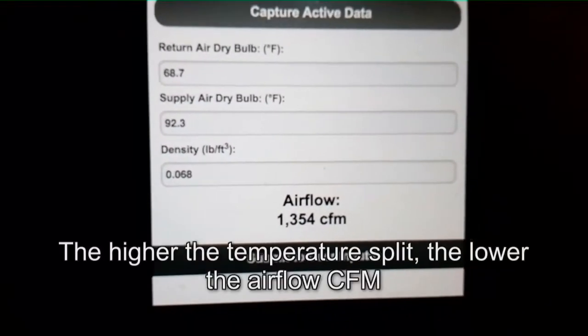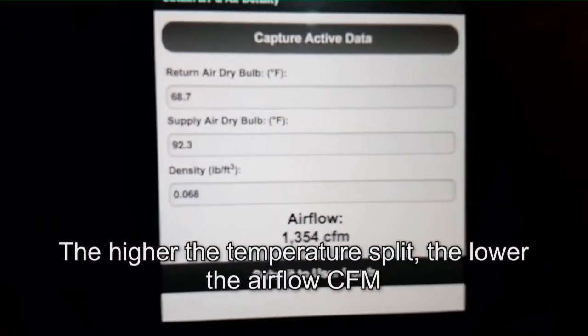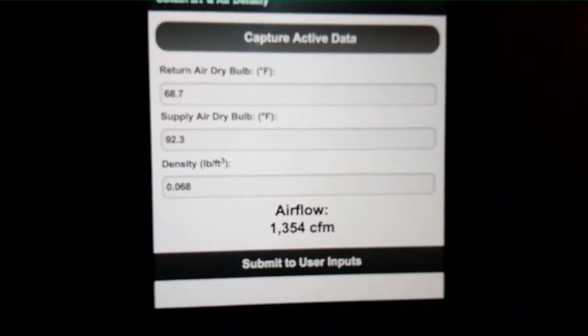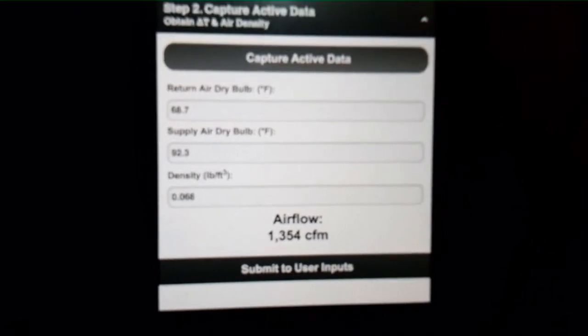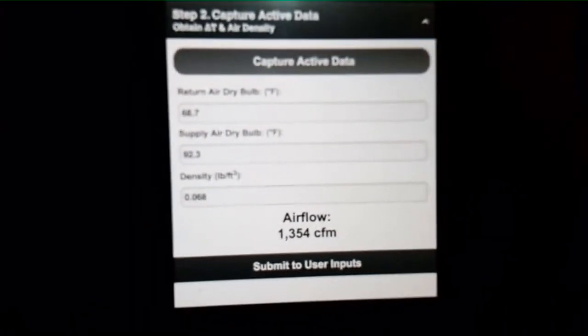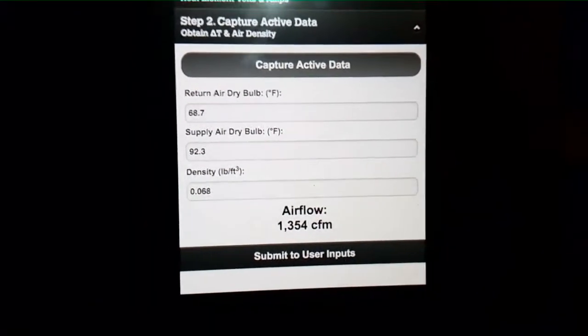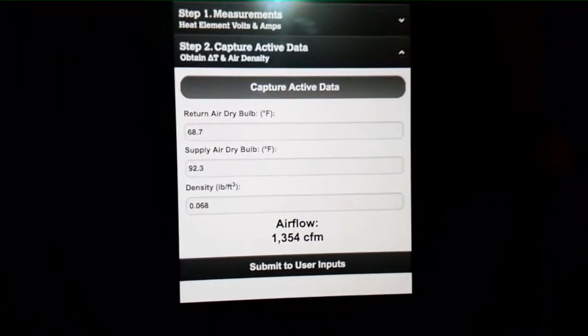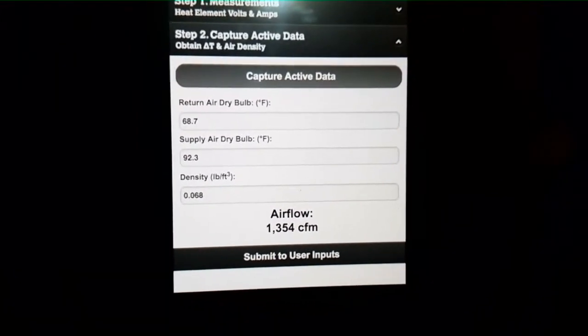As the temperature goes up, I'm going to let it keep going. That airflow will go down. If the temperature split is lower, it's because there's excessive airflow, but I'm still letting the machine balance out. But right now it says 1354. We'll give it a couple more minutes and we'll check it again. It's not too far off.